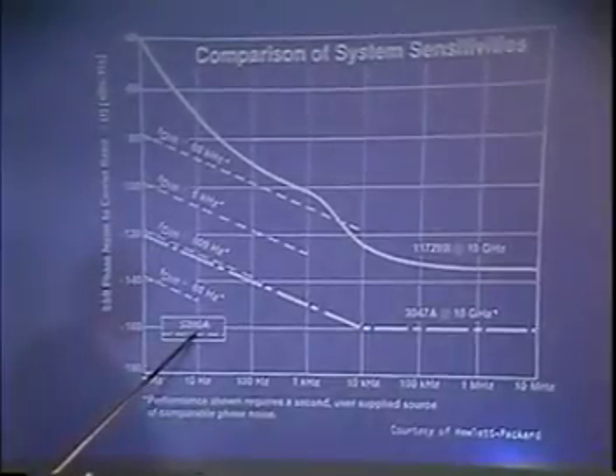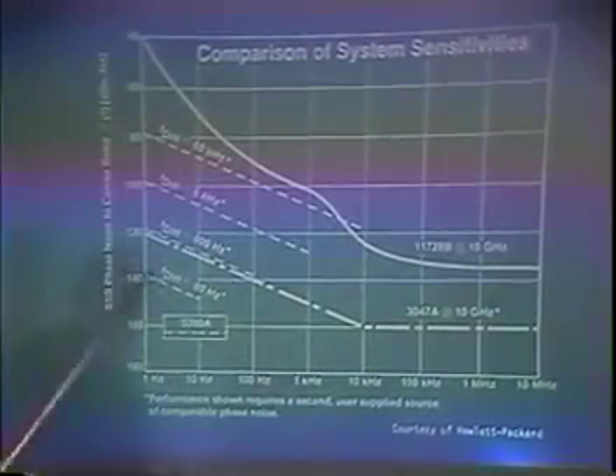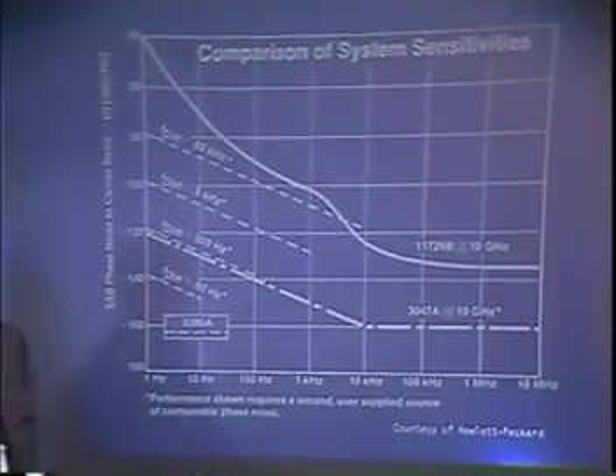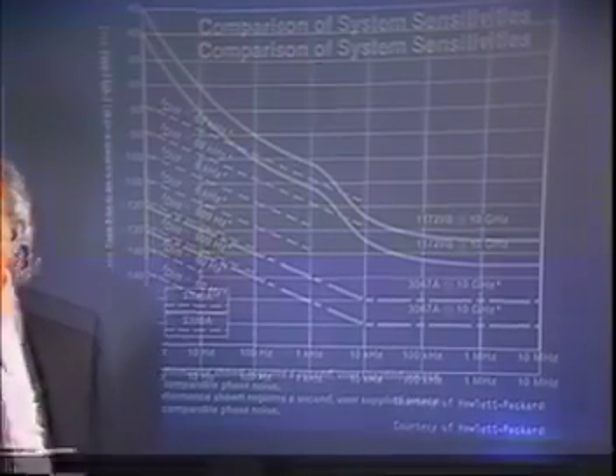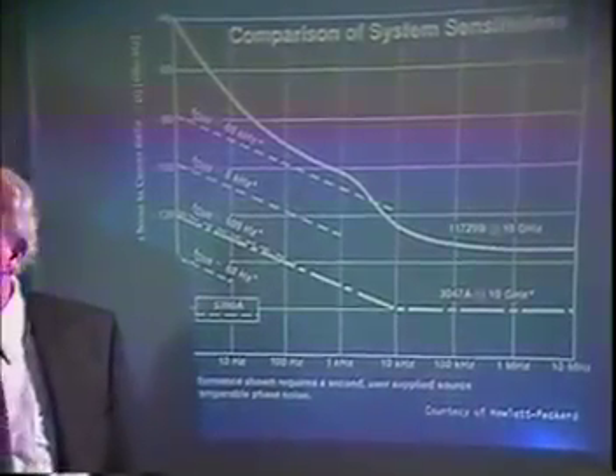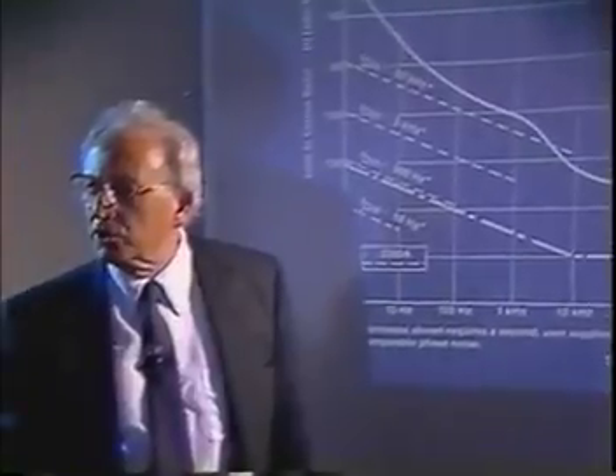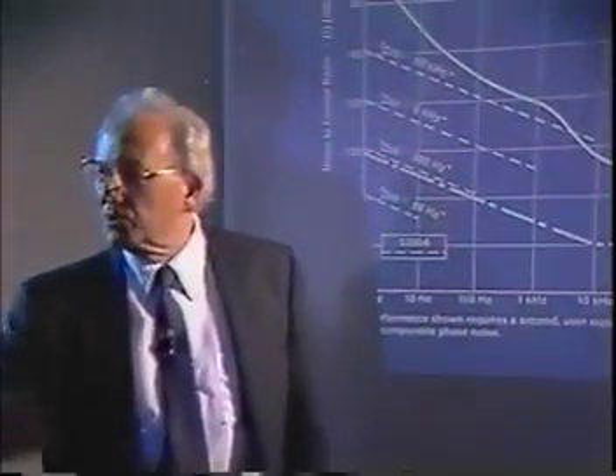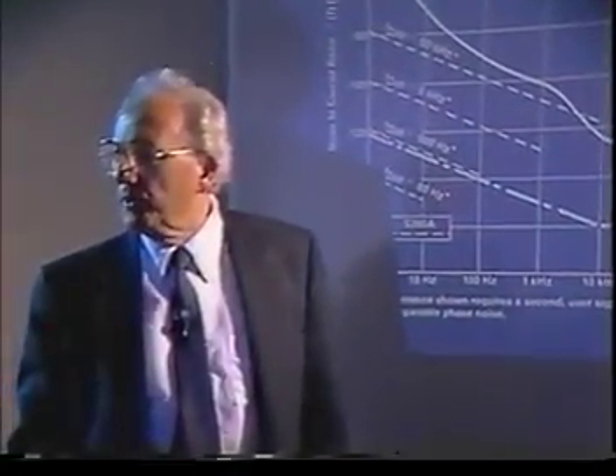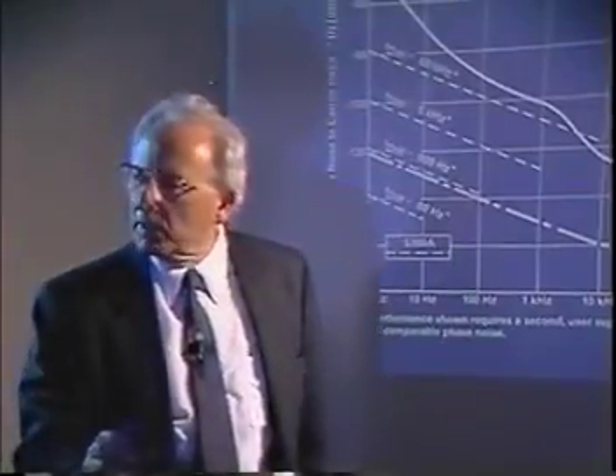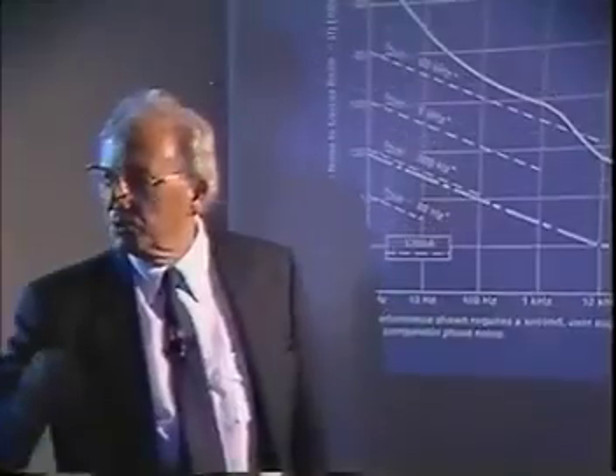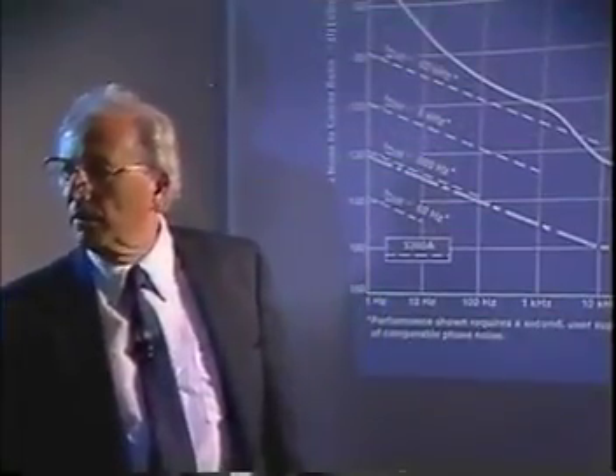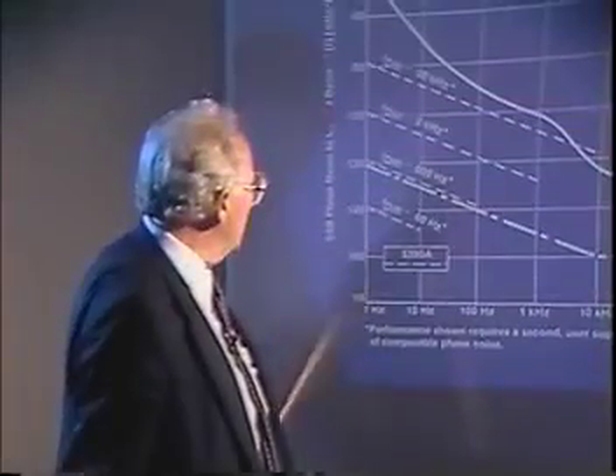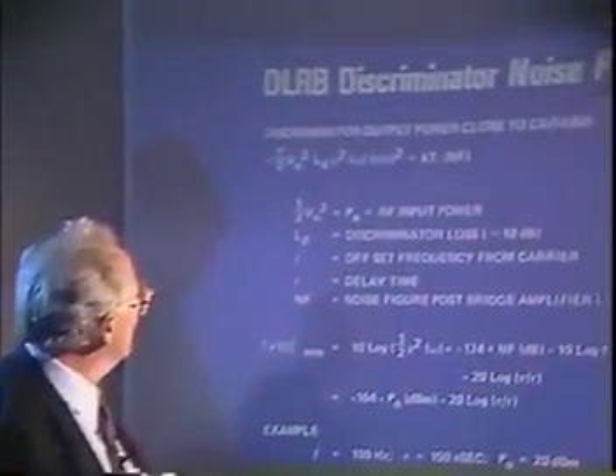All of these, the 5390 here is a time domain type of measurement system, which will measure way down, very close to the carrier. But it's a time domain, which means you take a counter and you measure the zero crossings of sets of measurements, over a period of time. You make a set of measurements with the counter, another set, another set, and then you calculate in the time domain, you calculate this spectral density.